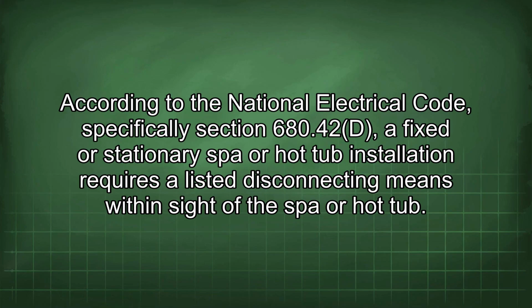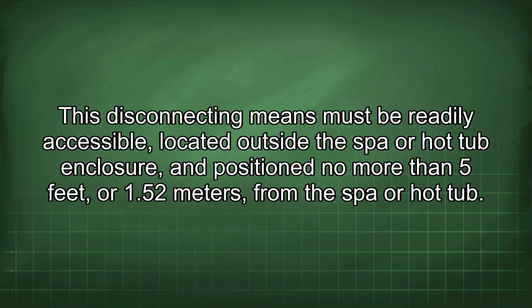According to the National Electrical Code, specifically Section 680.42(D), a fixed or stationary spa or hot tub installation requires a listed disconnecting means within sight of the spa or hot tub. This disconnecting means must be readily accessible, located outside the spa or hot tub enclosure, and positioned no more than 5 feet, or 1.52 meters, from the spa or hot tub.